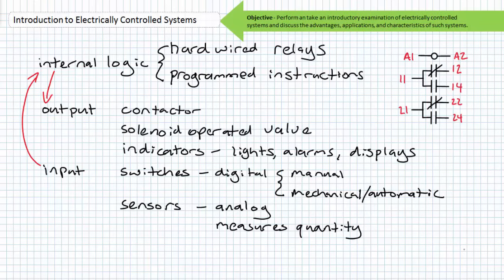A control relay is a device internal to the logic of an electrically controlled system and only switches control level signals. A switch associated with a control relay could turn on or off a coil or a solenoid, which in turn would drive a primary load. Control relays are seldom used to directly drive a load and would only be found doing so in the lowest of low-power applications. Control relays, as the name implies, switch only control level signals.